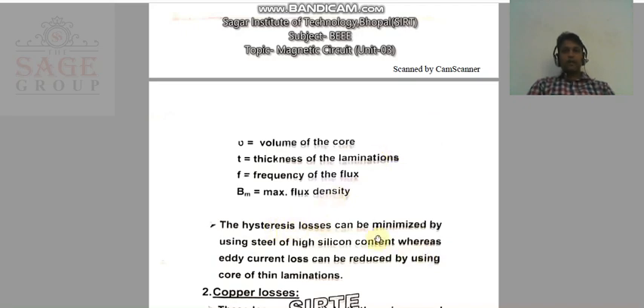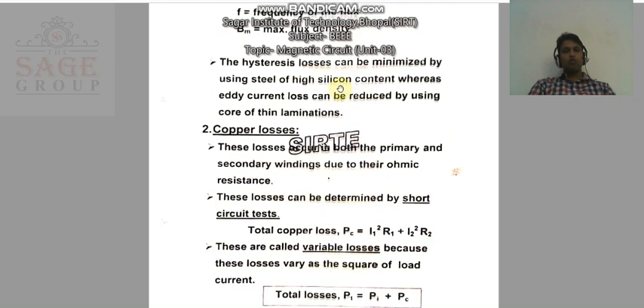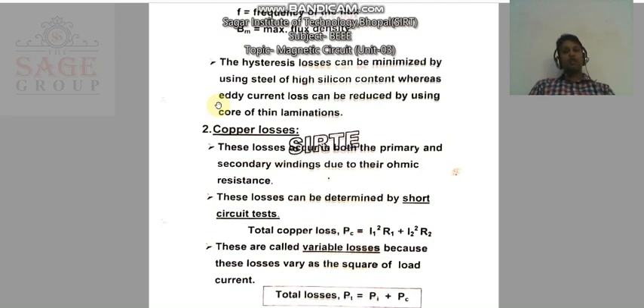Hysteresis loss can be minimized by using steel of high silicon content, whereas eddy current loss can be reduced by using a core of thin laminations. The thin plates of the core are combined, but every plate is insulated from the others. By using these two methods, we can reduce the core loss of the transformer.